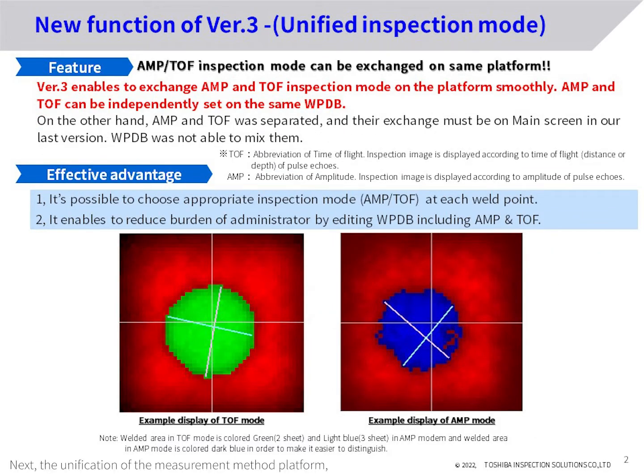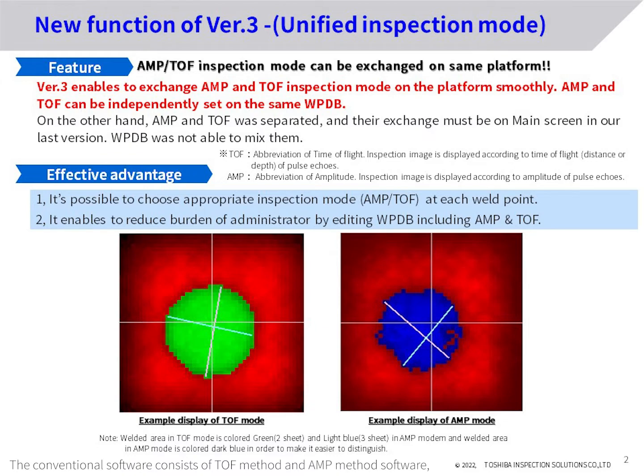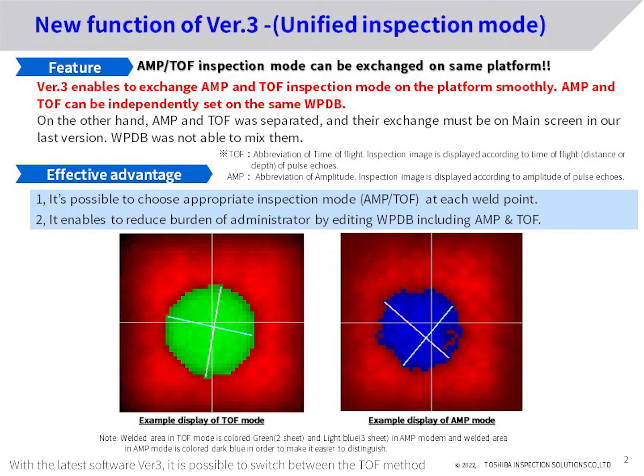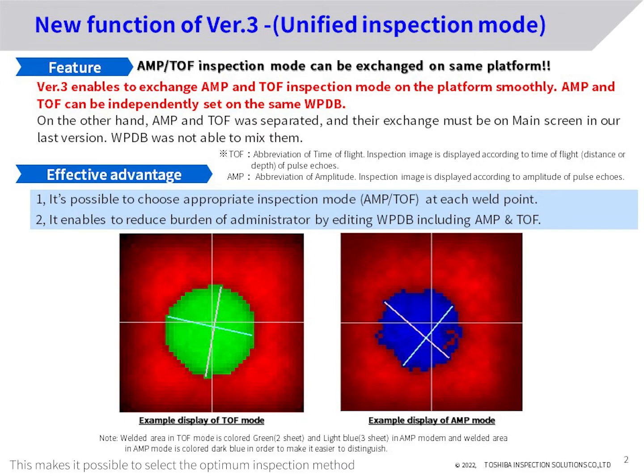Next, the unification of the measurement method platform, which is a major change from the conventional software, will be explained. The conventional software consists of TOF method and AMP method software, and it was not possible to quickly change the measurement method. With the latest software version 3, it is possible to switch between the TOF method and AMP method within the same inspection program by unifying the measurement method platform. This makes it possible to select the optimum inspection method for spot welds in various welded conditions.